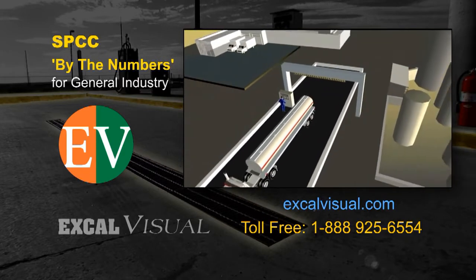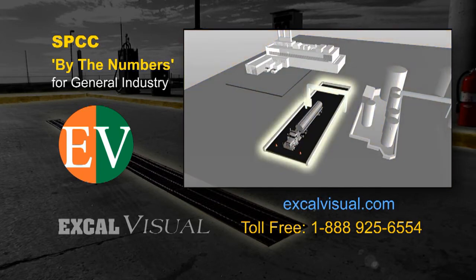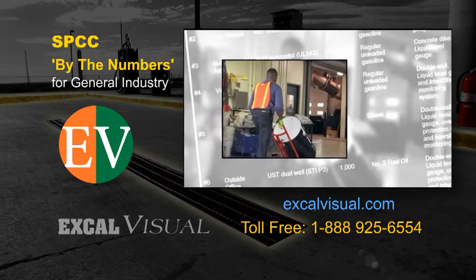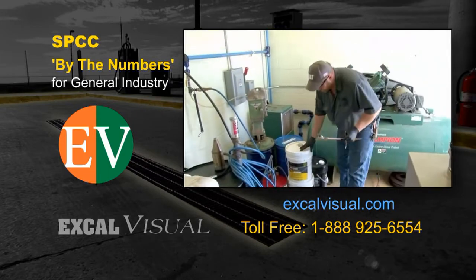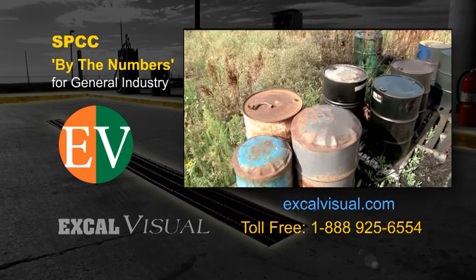This tank truck offloading station is equipped with a low berm all the way around it. It allows the truck to drive in and out, but at the same time provides secondary containment in the event of a release. Locations for storing portable oil containers, like drums, are also specified in the SPCC plan. To minimize the potential for a storage capacity violation, unneeded or empty containers should be removed from a site as quickly as possible.